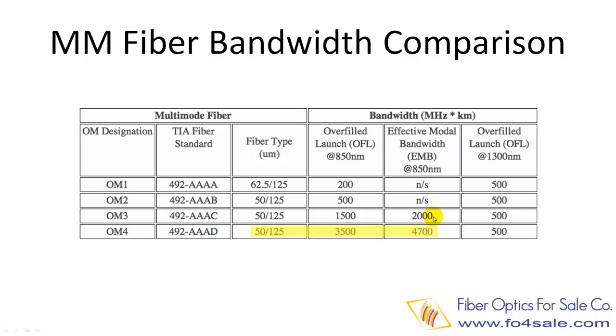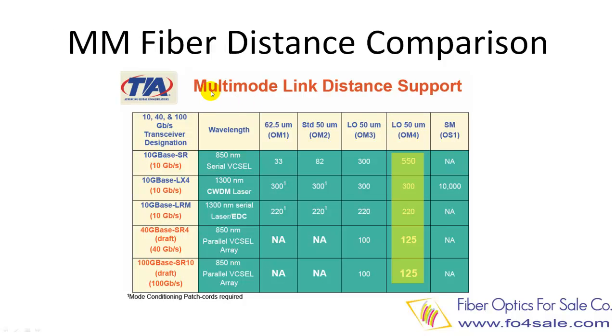We should focus on the EMB bandwidth column. OM3 fiber is also laser optimized for VCSEL lasers, but it only has a 2000 MHz·km EMB bandwidth, compared to OM4 fiber's 4700 MHz·km EMB bandwidth. This table shows the maximum distance multimode fibers can carry for different transmission data rates. It shows that OM3 fiber can carry 10 Gbps SR to 300 meters, whereas OM4 fiber can carry up to 550 meters. For 100 Gbps SR, OM3 fiber reaches 100 meters, whereas OM4 fiber can do it to 125 meters.